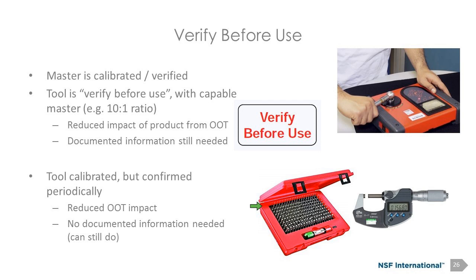So using a micrometer and having the folks using the different pins confirm them against the micrometer on a daily basis or a per shift basis or whatever it might be is the more economical way of approaching it. And that's great as long as we still meet the documented information requirements. We still need to show that tool was tied to this tool that's then tied to a certificate or some documented information about fitness for purpose.